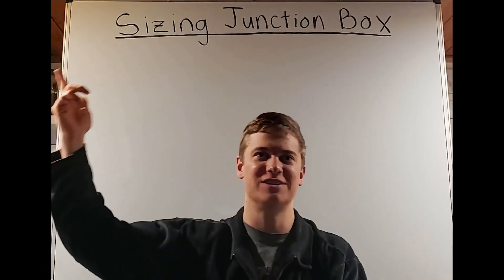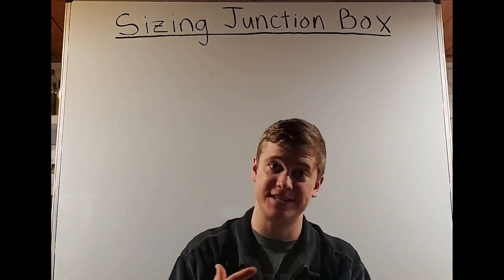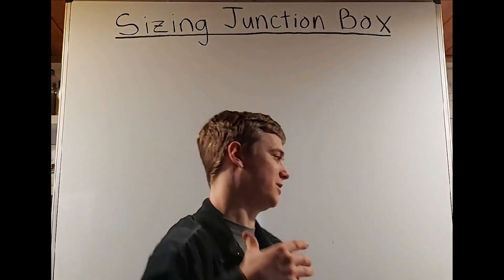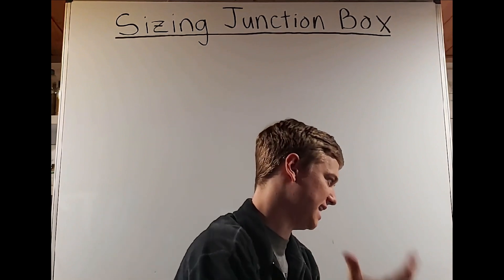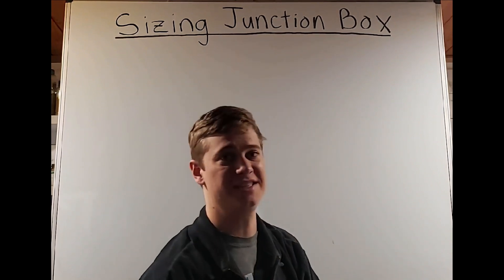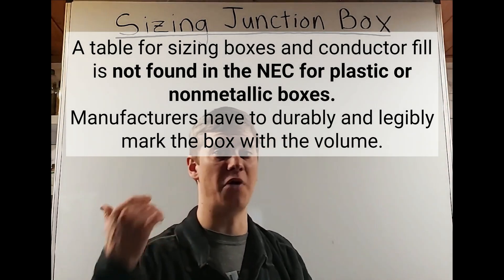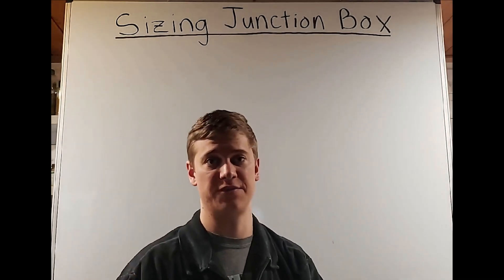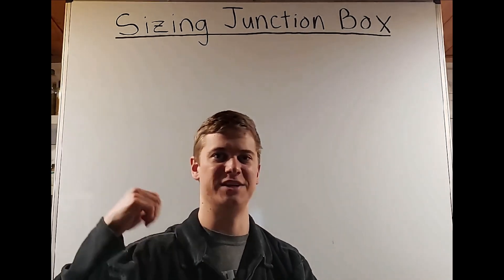Welcome to this video, all about sizing junction boxes. You're going to need your NEC code book for this. You're going to want to go to Table 314.16A and 314.16B. Table A covers metal boxes and B is the volume allowance, required per conductor. If you aren't familiar with this, it will explain itself as we get to it.